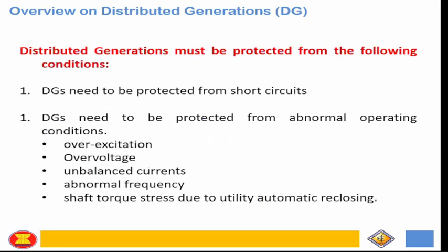Okay, and then distributed generation must be protected from the following conditions. DG needs to be protected from short circuit, of course. If you are the DG, you need to gather data from the utility, what the fault level is at that connection point.